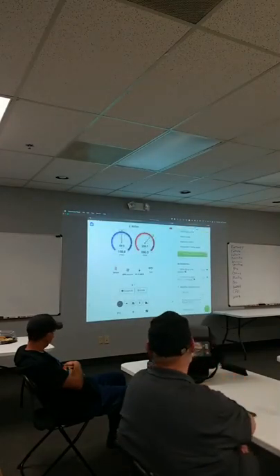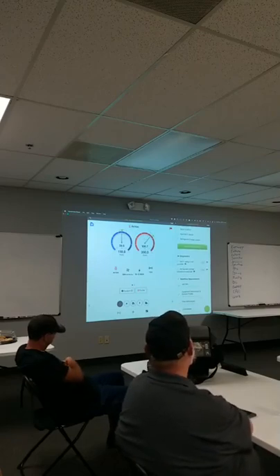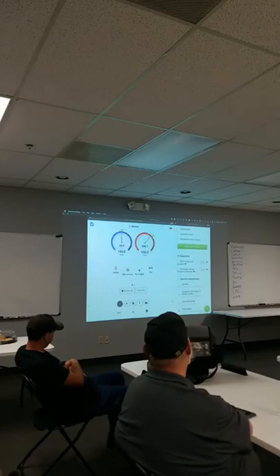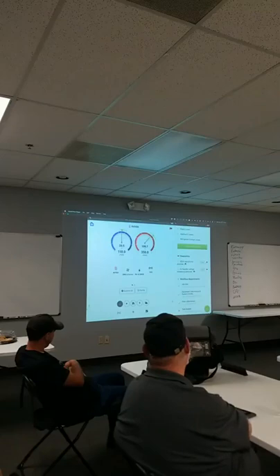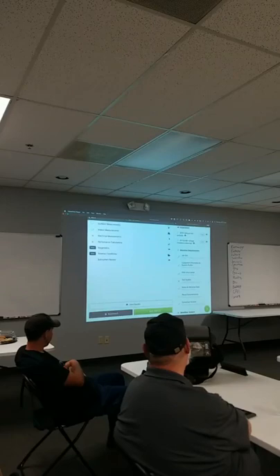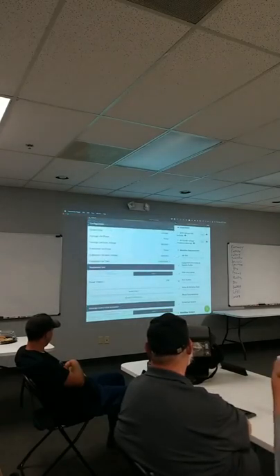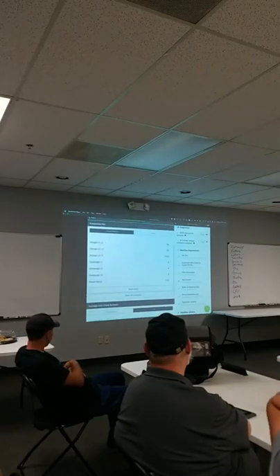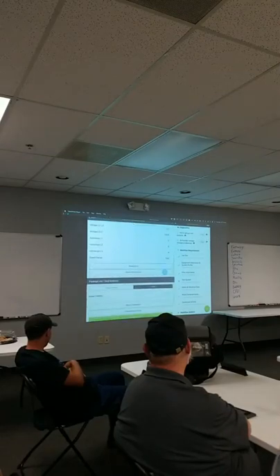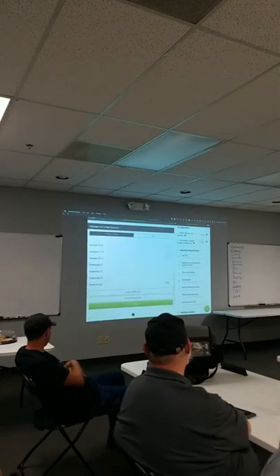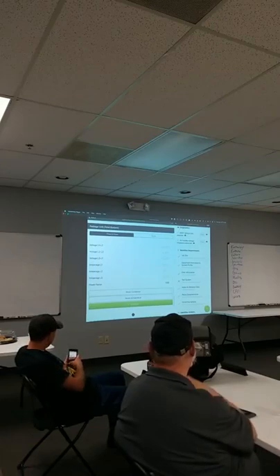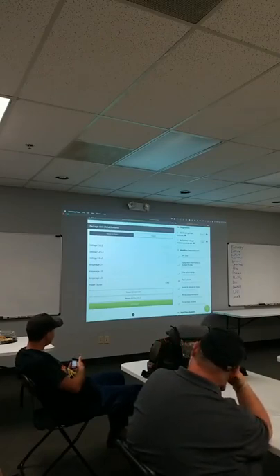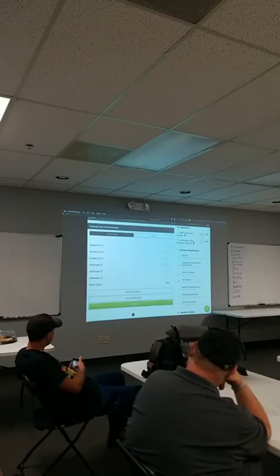All right, in this case we put in some demo data, and because I used demo data, the SEER rating's not possible, and air handler voltage imbalance is detected, because the demo data is for single phase equipment. So it's already doing some diagnostics. If we go to test the system, we've got all our outdoor and indoor measurements in, and we put in our electrical measurements, in this case phase-to-phase. This is why I have an imbalance in phase, because this is all residential data I put in for the measurements. On the meter, on the Redfish, we have an auto capture, so you can literally move from L1 to L2. It'll beep and tell you it's got the reading. It detects when you take it off power and put it back on power, and it'll do all those different tests.